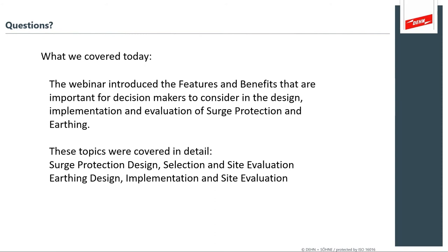And remember, the IEC has the conservative assumption that 50% of the lightning current is being distributed into the soil and 50% is being diverted back into the electrical installation. So in other words, if you design a system for LPL3, which is a 100 kA lightning strike, the IEC assumes that 50%, 50 kA, gets distributed into the soil. Well, 50 kA might be seen by the surge protection devices. So for this LPL3 design you need to make sure you have a surge protection device that can handle a maximum of 50 kA lightning current.